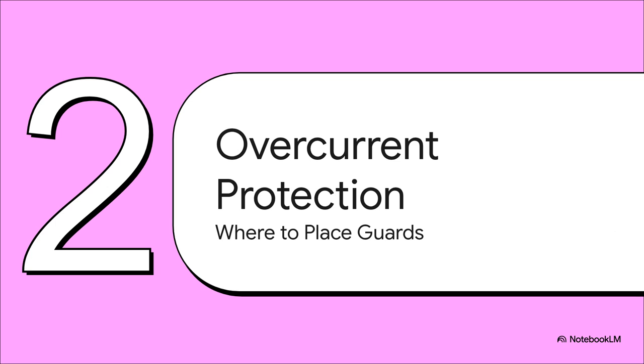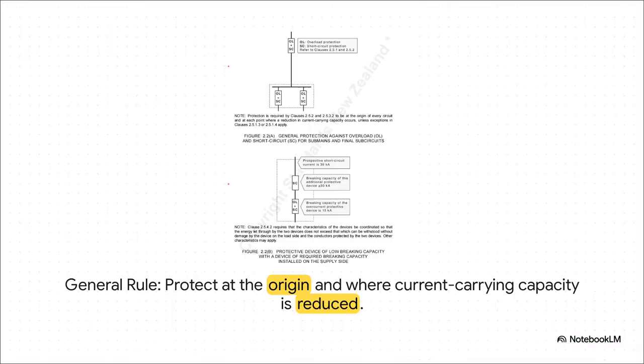So we've figured out the what and the why of protection. Now, let's talk about the where. Because where you physically put these protective devices is every bit as critical as picking the right one. This diagram here shows the golden rule. You can see the protection is right at the start of every single circuit. And it doesn't matter if it's a huge submain or a tiny lighting circuit, the rule is simple. Put protection at the origin. And also, you need it at any point where you switch to a smaller cable that can't carry as much current. It's just common sense, really.